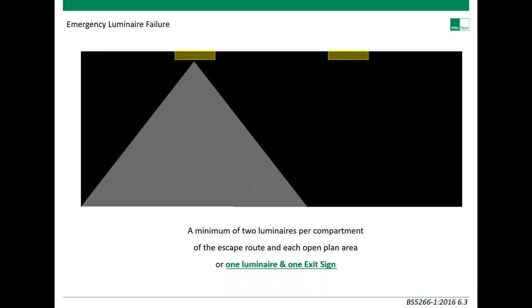To avoid emergency luminaire failure leaving an area unlit, it is considered good practice to have a minimum of two luminaires per compartment of the escape routes and each open plan area, or one luminaire and one exit sign. In the event of a luminaire failing, there is another one able to provide some form of emergency lighting for that compartment or room.